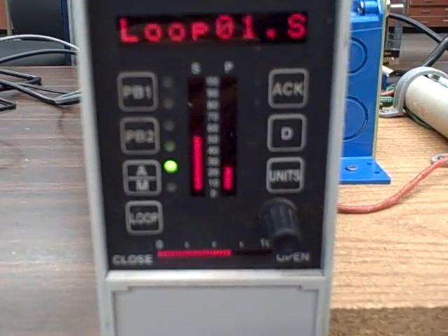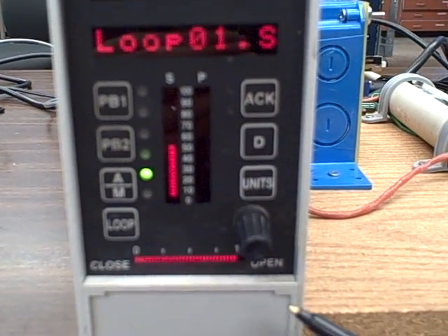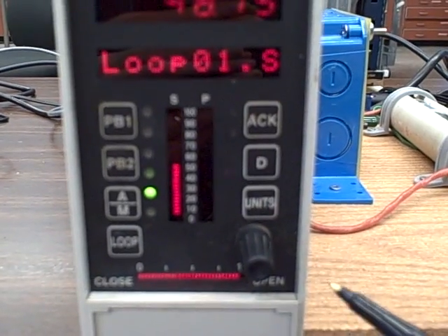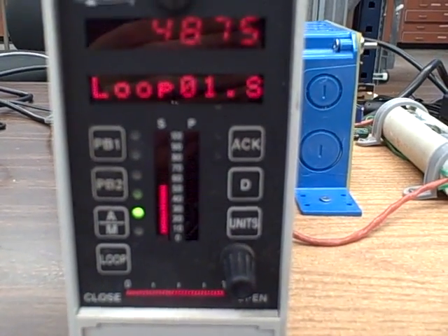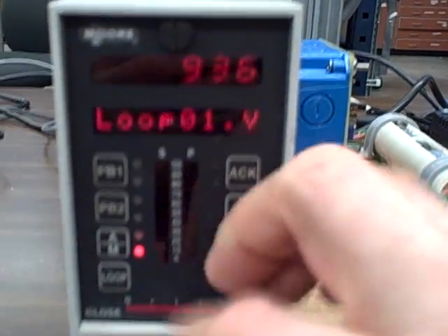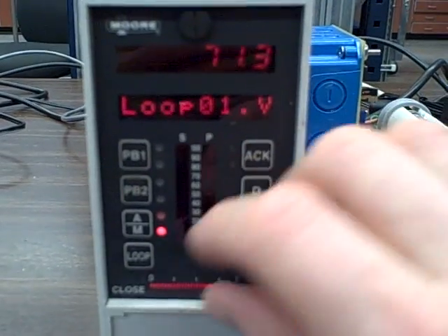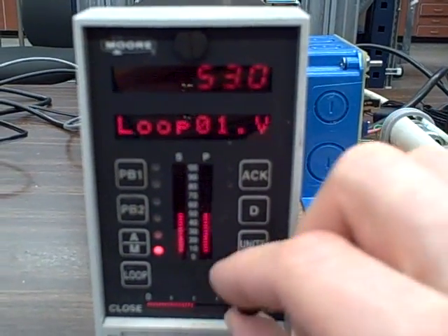There we go. Something slowed the motor down. In response, the controller sent a higher output signal, which in this case, unfortunately, drives the motor even slower, and so on until the motor's at a full standstill. I can go back to manual mode, decrease my output signal to make the motor spin again. Remember, with the backwards motor speed drive is kind of confusing.